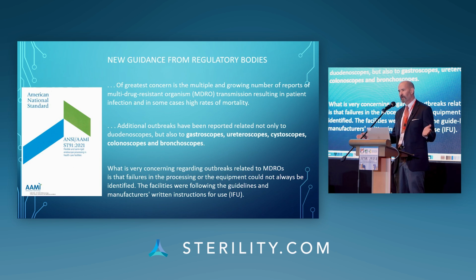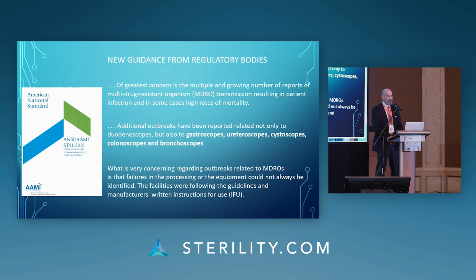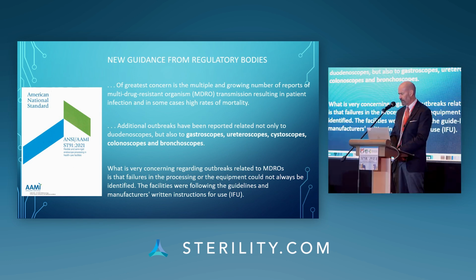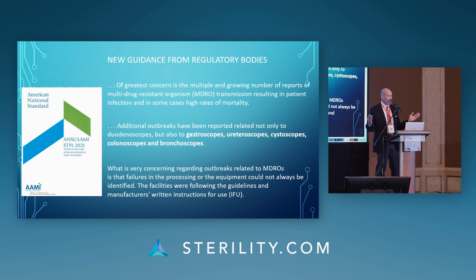And this last point I'll draw your attention to. This is what I think is most significant. AAMI and other groups that have done deep research into these outbreaks have discovered a very, very disturbing fact, and that is that in almost all cases, and I read from this, the processing or the equipment could not always be identified. Failures in the processing or equipment could not always be identified. The facilities were following the guidelines and manufacturers' written instructions for use. The equipment was working. The operators were doing everything properly. The organisms were surviving. At this point in time, the standard of care is high-level disinfection, and again, the organisms were surviving this processing.